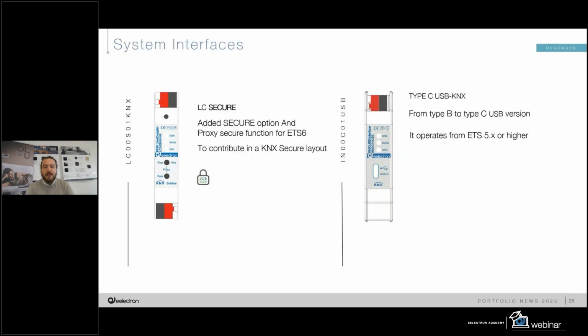Going ahead, we have an upgrade of our interfaces. This is because, as you can see, KNX Secure is becoming more popular in systems and project specifications. And in order to forward messages between the lines in KNX Secure, you will also require a line coupler that supports KNX Secure. So we released a new line coupler with the KNX Secure option that can be activated. In addition, if you are using ETS6, there is a new function that you can enable in the line coupler called proxy secure. It means that you can have one side of the line coupler unsecure that converts to secure mode, with secure telegrams to the other line.